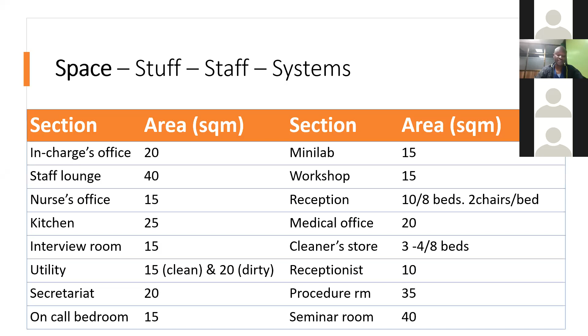Still talking about space, the number of ICU beds is conventionally agreed to be about 5 to 10% of the hospital's total bed capacity. National health insurance funds in some countries have guidelines for what they would consider to be an ICU. In addition to these features, the guidelines will stipulate the minimum number of beds in an ICU, usually a minimum of 6 and an optimum of 8 to 12 beds. But in other countries, universal coverage is preferred and the service available is provided to as many people as possible. Minimum interbed space is about 1.75 meters, or a floor area for a bed space of about 20 square meters in a common room, or 25 square meters in a single room. The whole ICU should be at least 3 times the total area devoted to patient care.